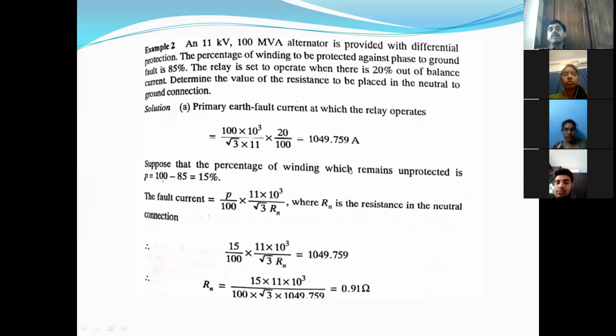Suppose the percentage of the winding which remains unprotected: 100 minus 85, because they said 85% is protected. Therefore, P is equal to 15%. We already know the formula from the previous problem: the fault current is equal to P by 100 into V by Rn. Here Rn is unknown. P is 15%, V is 11 kV, so 11 by root 3 into Rn is equal to the fault current. We have already calculated it from the 20% out of balance current: 1049.759. From this you can calculate the Rn value as 0.91 ohms.